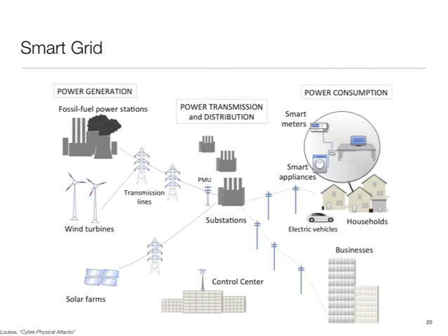I think this stuff came out of research at Virginia Tech many years ago. These are essentially sensors which sense the AC cycle. The AC cycle is 16 milliseconds. I believe they sample this AC cycle 48 times, if I recall my numbers right, and they do it in synchrony. That is, the same sample is taken identically all over the grid. To achieve that level of synchronization, they use GPS. So each PMU has a GPS attached to it, used not for location, but for timing.